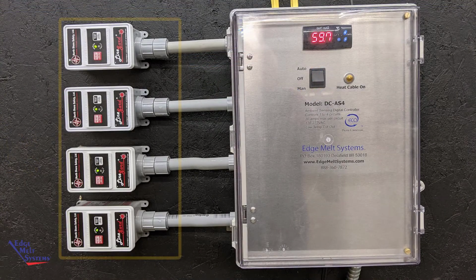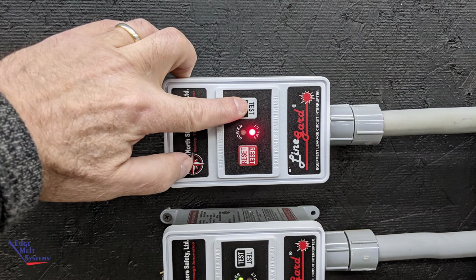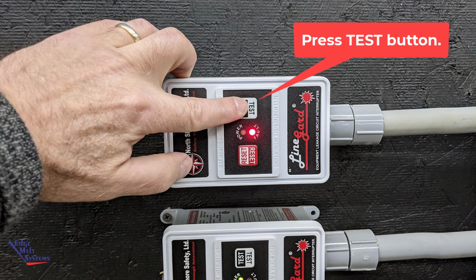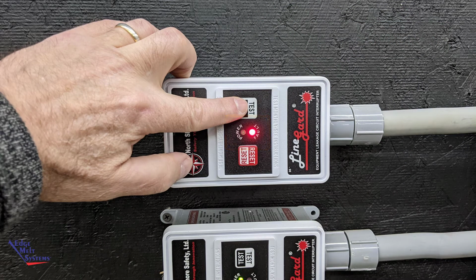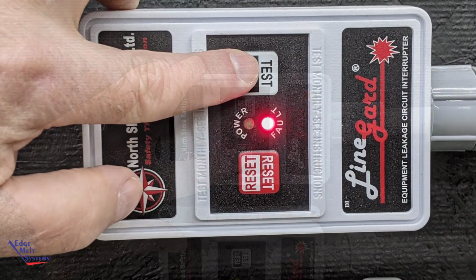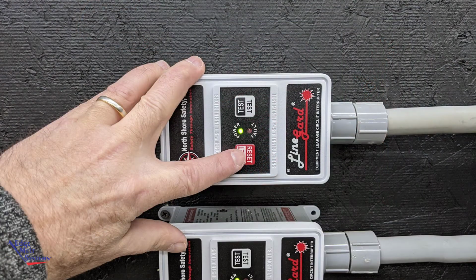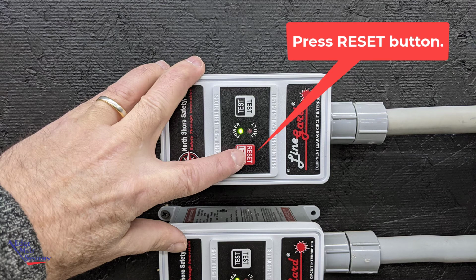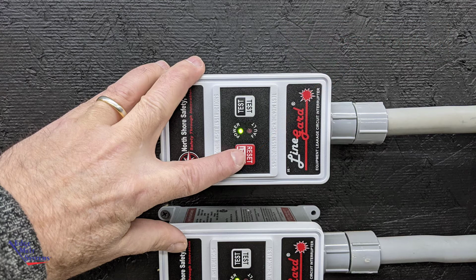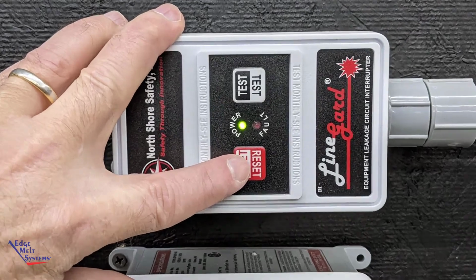We recommend wiring the EPD units on the line side of the controller, and this allows the units to always be illuminated even when there's no power being sent to the heat cable. To test the EPD units, press the test button and the red indicator light will begin flashing. To reset after testing, press the reset button and the blinking red light will turn to the green solid LED light.